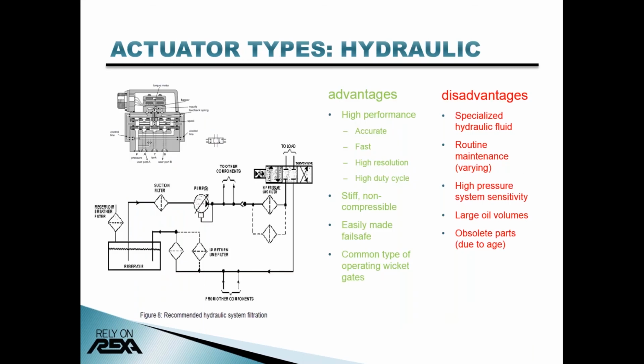Using hydraulics is the most common method to operate turbine governor control valves and turbine bypass valves. These systems provide high frequency response, fast speeds with low dead time, high resolution, and fail-safe capabilities, making it ideal for this type of service. These benefits, though, come at a cost. Oil volume is typically very high and requires routine oil maintenance.